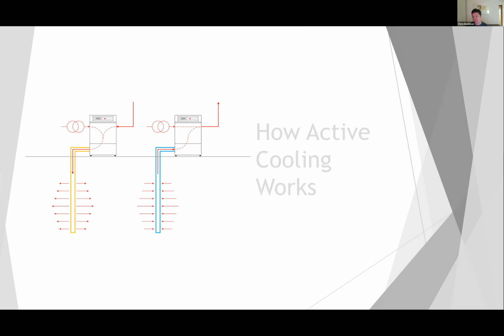Okay, and just a follow-up question: is there actually a minimum size of system to be effective? If you're looking at a small domestic or small commercial size, maybe 10, 20 kilowatts, is it still effective, or do you need to be up in the hundreds to thousands of kilowatts? No, if you're looking at a small reversible heat pump, it can be effective. I've done systems down even at 3 kilowatts for district-type apartment buildings and so on, where cooling is increasingly becoming a problem. So no, it can be effective really at any size.